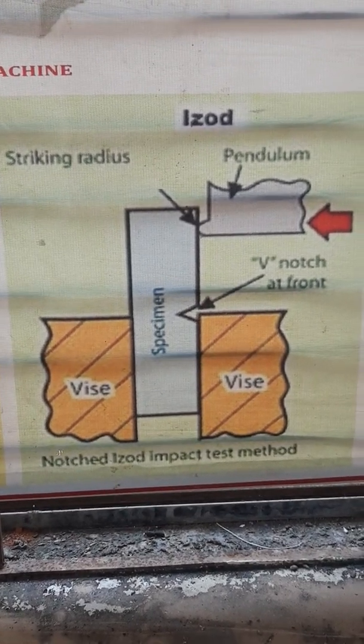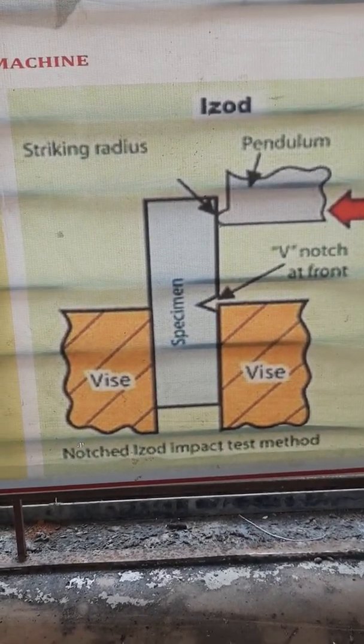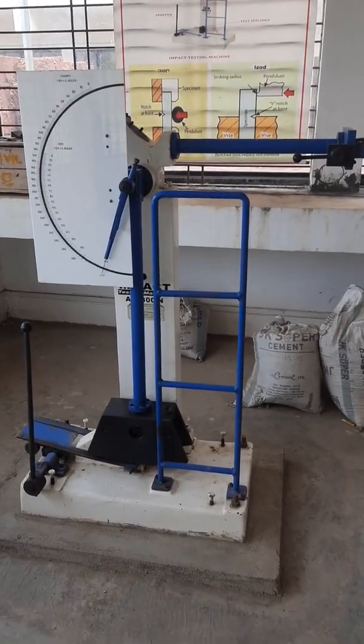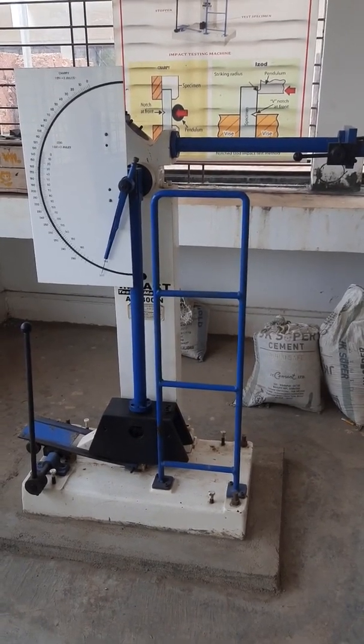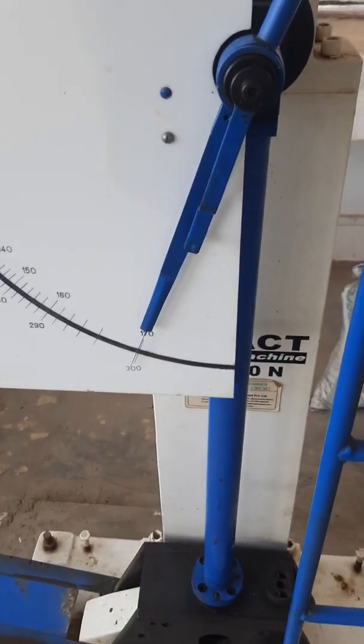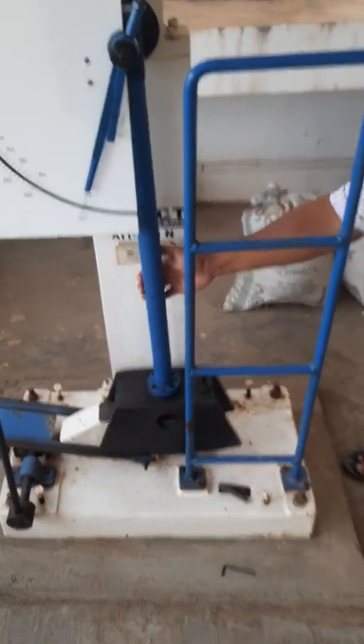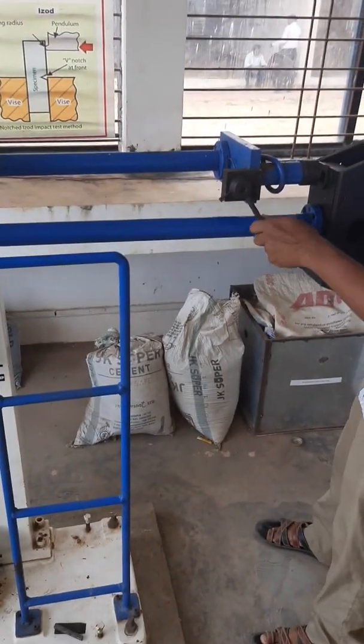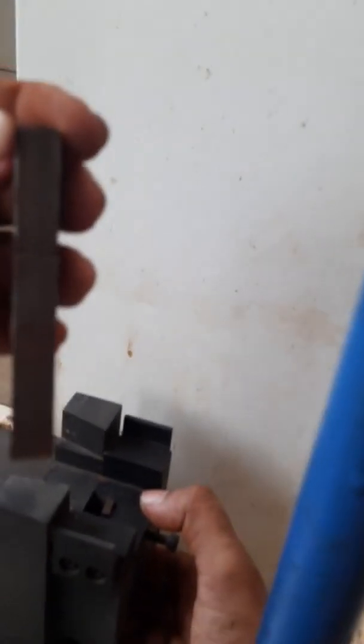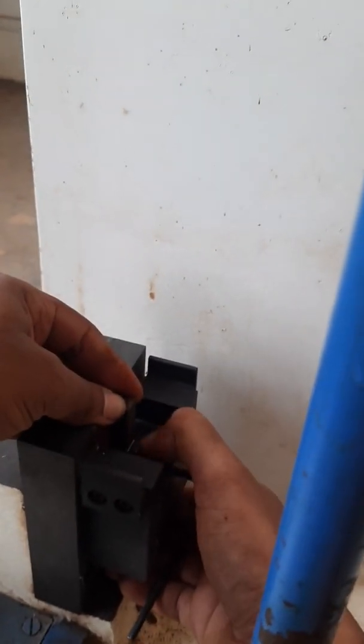This schematic diagram shows the specimen mounting for the Izod test. The specimen is mounted vertically with the V-notch facing towards the pendulum. This is the impact testing machine on which both Izod and Charpy tests are carried out. Set the pointer to the zero mark, then raise the pendulum to 90 degrees and latch it. The specimen is placed in the fixture with the notch facing the pendulum side.